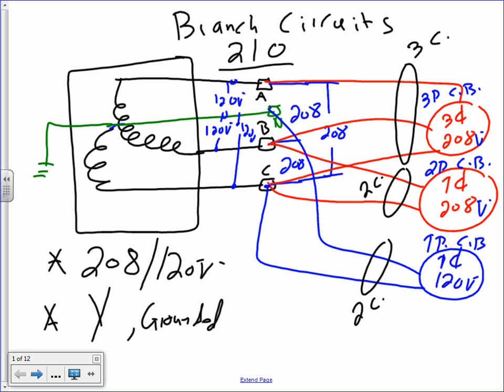I want you to fully understand that the power system that we're using for this building is a 208/120 system. It's coming from a Y, and it's grounded. Can I have thumbs up, Chad? This is the transformer that tomorrow, Carrie, you're going to grab and drop outside the building in Revit. It's going to be a delta, Y grounded transformer. Can I have thumbs up, Chad?